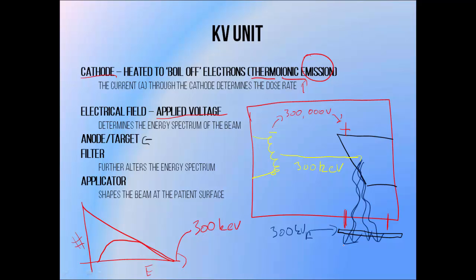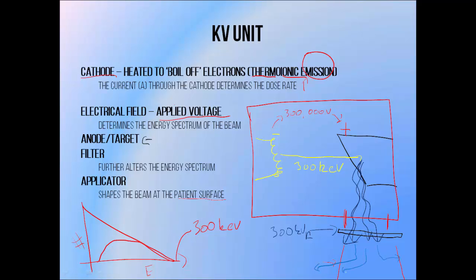When treating patients, we generally insert an applicator below the filter. It's normally a cone of metal which contacts the patient's skin, allowing the beam to be given a clinically useful shape with very sharply defined edges. It's important to shape low energy photon beams close to the patient's skin surface, because low energy photons can be scattered in the air, which results in them moving in directions other than that in which the beam is pointed, so they tend to hit structures that aren't your target.